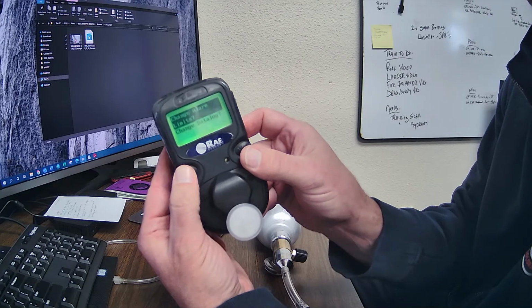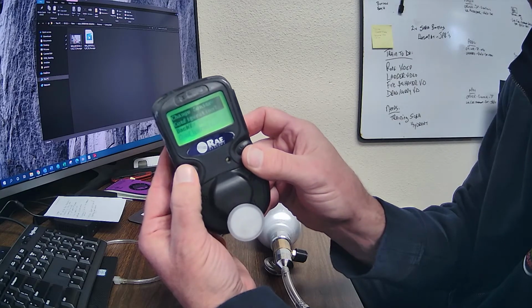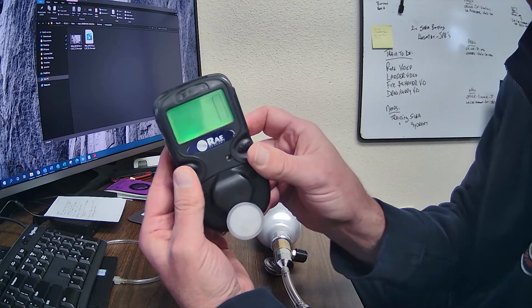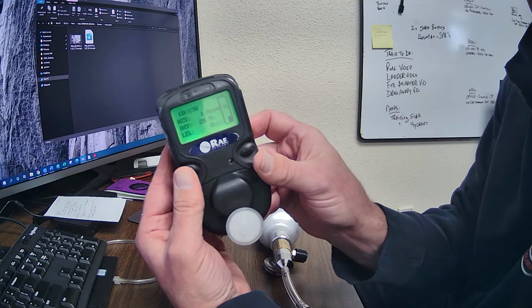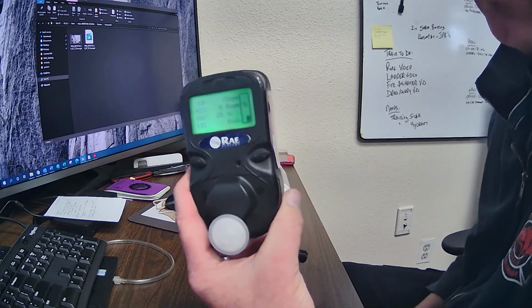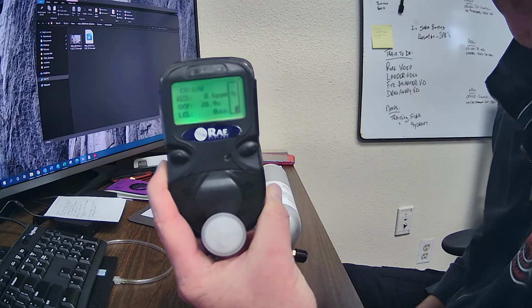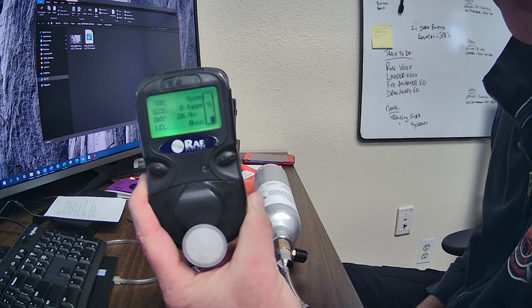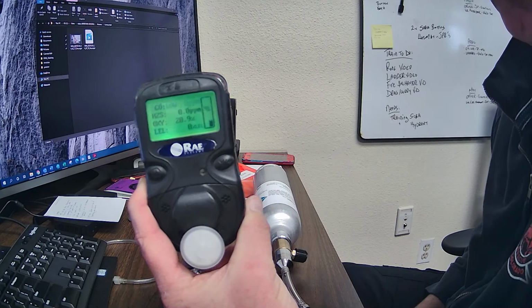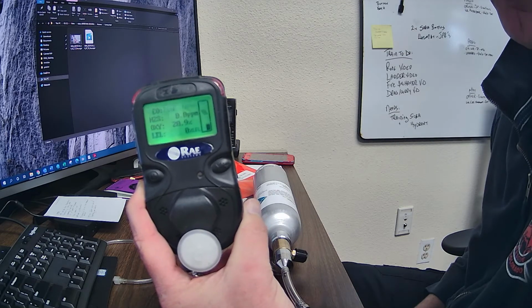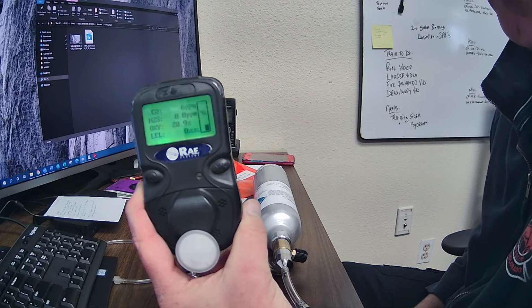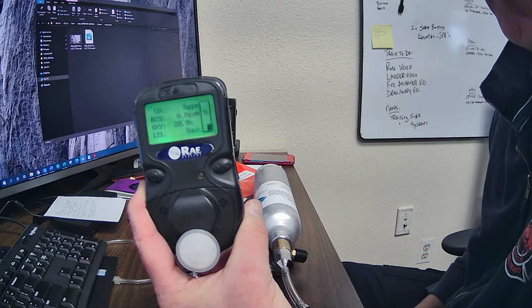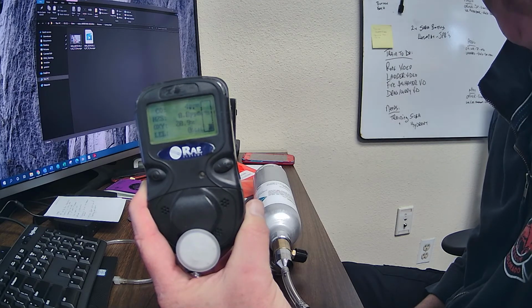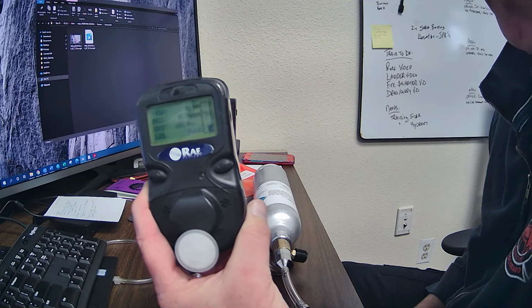You go all the way back. So you're just scrolling through all the stuff that you went through to get there. You have to go all the way back. Okay, it's got a 0 out. So it was low, and now that we're back at the original readings, it's got to go back to what the atmosphere is. This takes a minute or two because you just went through the calibration. And the CO sensor, I'm told, is the slowest sensor to get back. You can see it's dropping. It's going down to 4. And we could sit here, and it's going to go back down to 0 because I hope there's no CO in this office, but if there is, I will evacuate.